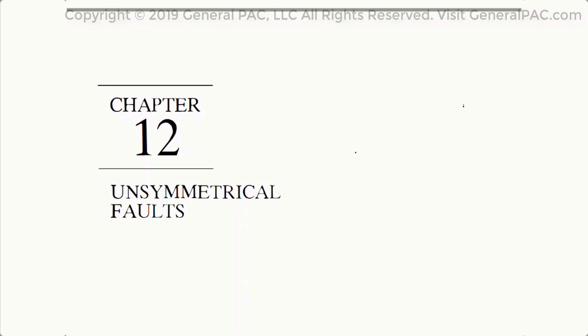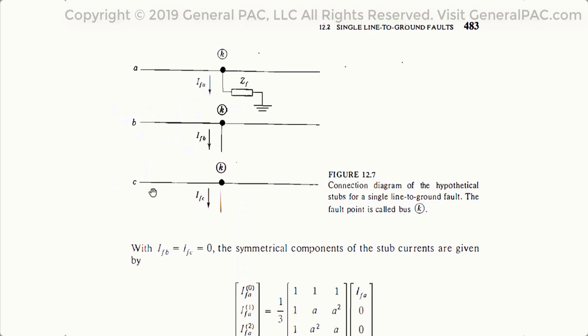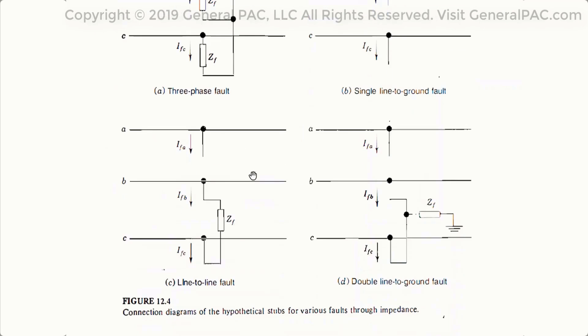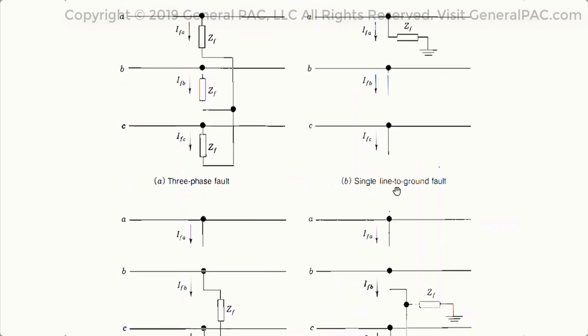In this video tutorial, Part 1, we're going to be reviewing a book by Grainger and Stevenson, specifically Chapter 12 on unsymmetrical fault types. The topic is building the symmetrical component sequence network diagrams. We'll cover a lot of different fault types: three-phase faults, single-line-to-ground faults, line-to-line faults, and double-line-to-ground faults — really delving into how to construct the sequence network diagrams based on the fault type and the equations involved.